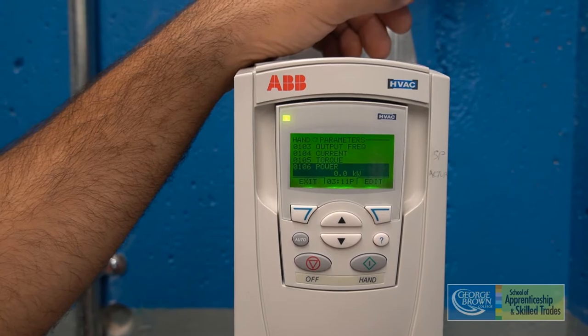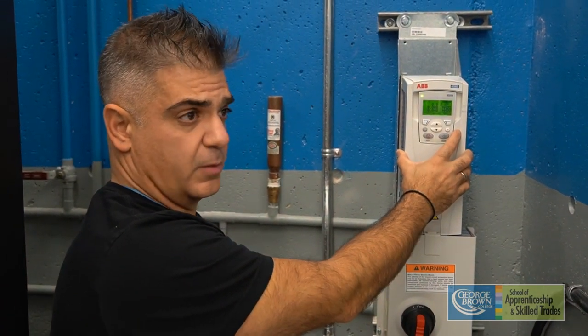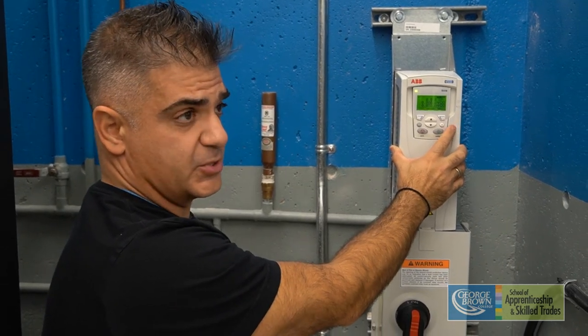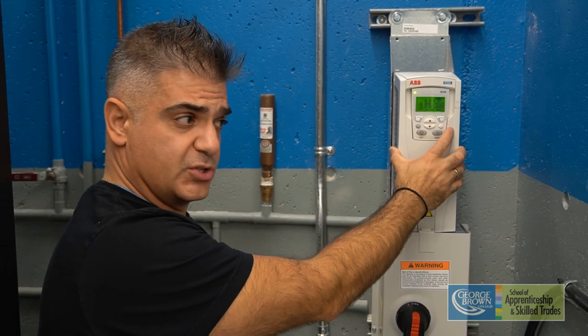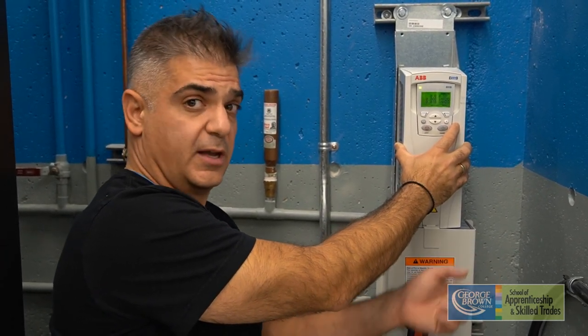The motor is not drawing enough power right now. Now that we've collected the data, we're going to use it to plot a fan curve — actually two fan curves: one with the dampers fully open and one with the dampers half open. We'll then be able to troubleshoot and determine whether the fan inside this VAV box is correctly sized using the data we've collected.